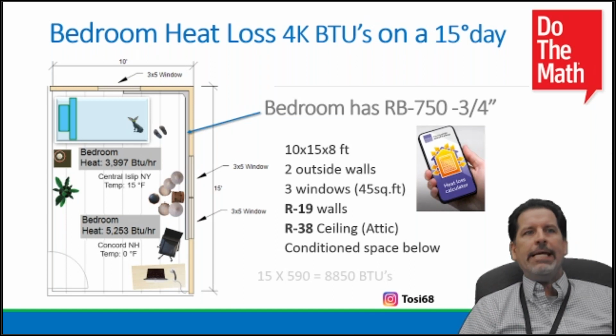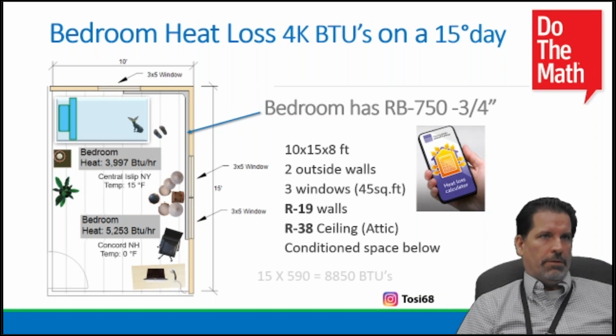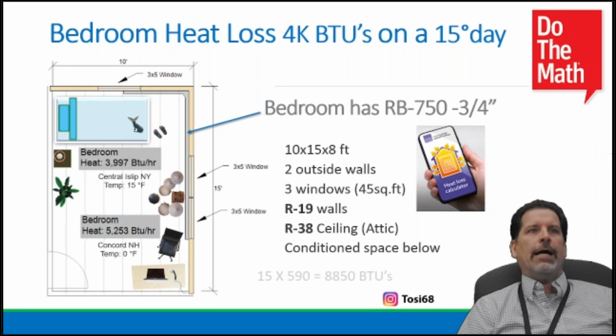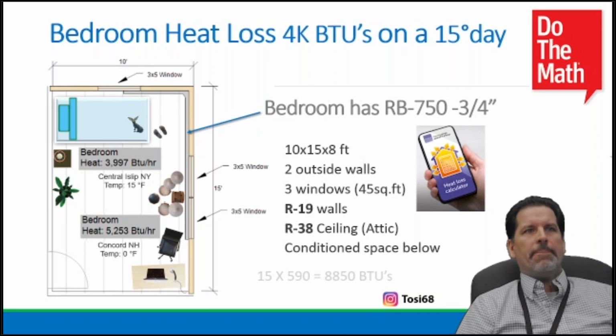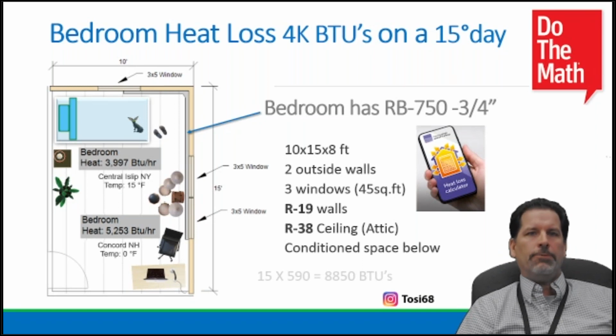It's 10 by 15, you know, 3 windows. We got an attic above. We got maybe a conditioned space below, some R19 in the walls, relatively newer construction. If this home was here on Long Island, I picked Central Islip for a 15-degree design day. That's what we're shooting for.